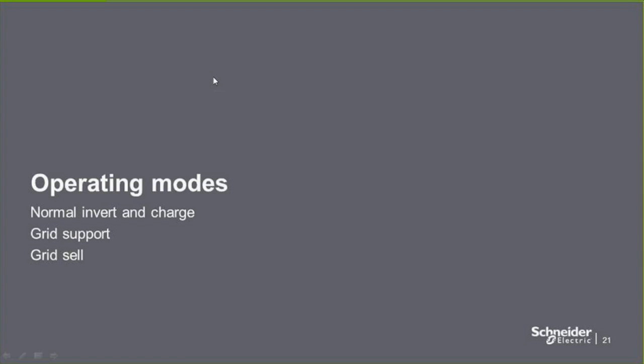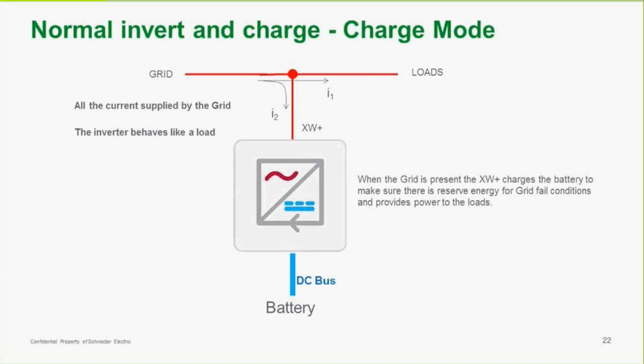So there are a few basic operating modes to the inverter, and everything else that the inverter will do kind of hinges off of these 3 modes of operation. So there's a normal invert and charge, and in the charge mode, the grid is supplying power to the loads, and we're also charging the batteries. So in this case, the inverter looks a little bit like a load until the batteries are charged up, and we're also powering the loads. And once the batteries are charged up, we have enough reserve energy in case there's a grid failure. Pretty basic.